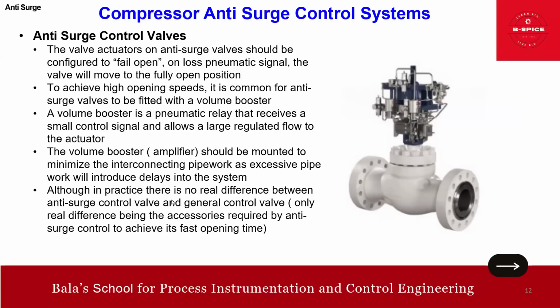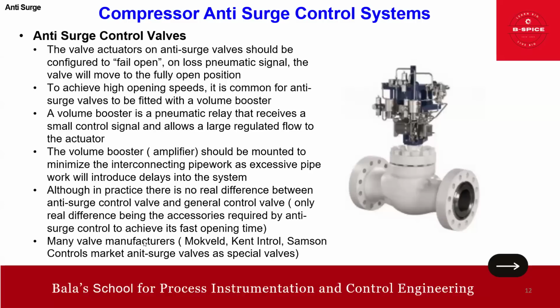Although in practice there is no real difference between the anti-surge valve and a general valve, the only difference is the accessories required by the anti-surge valve, meaning the volume booster. Many valve manufacturers are there, like Masoneilan, Fisher Control, and Samson. All these are specialized anti-surge control valves, friends.